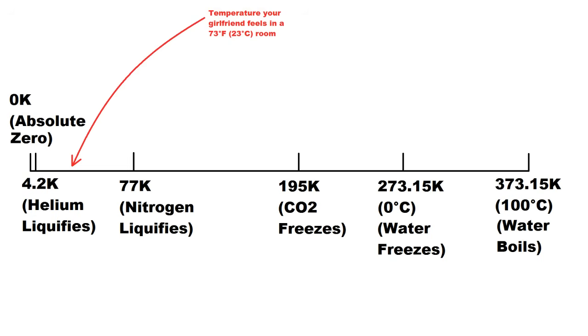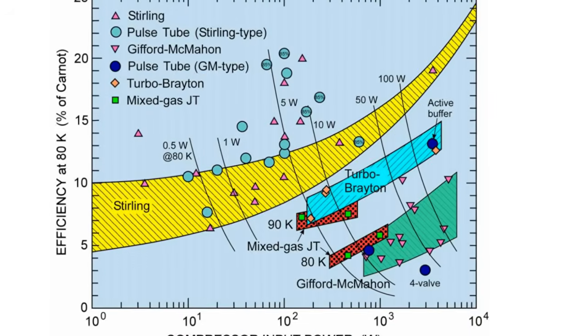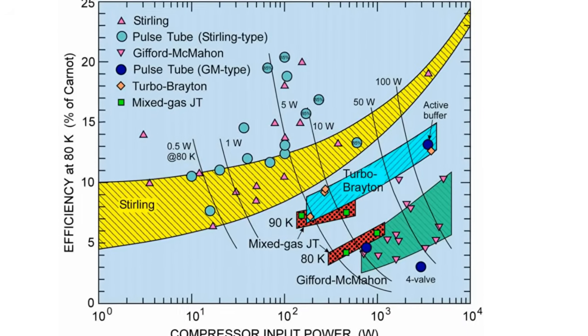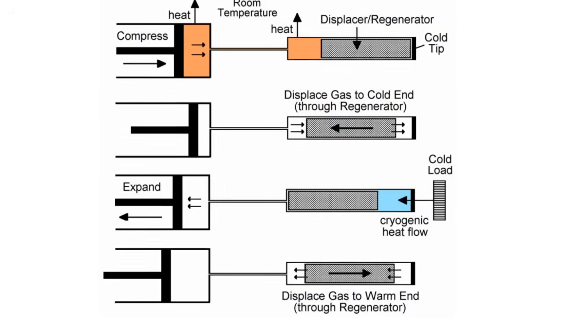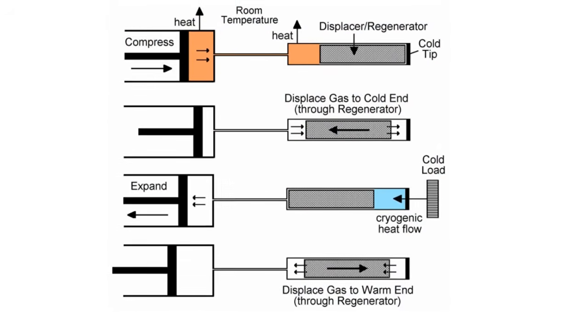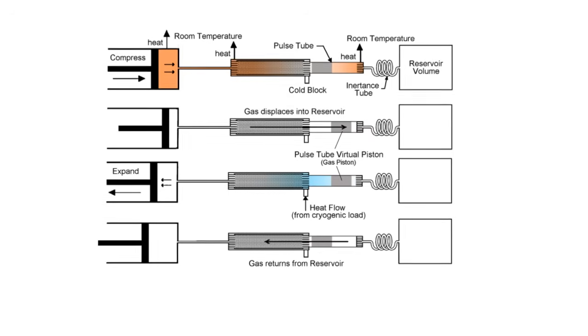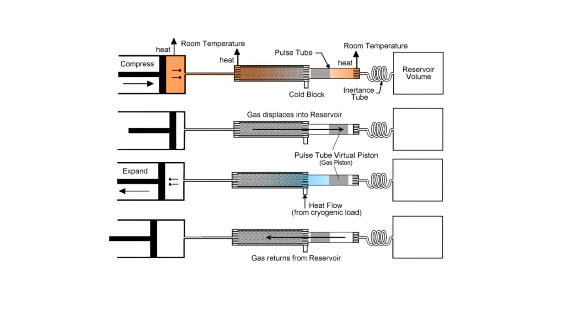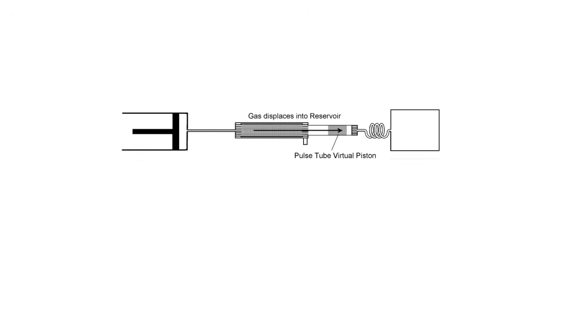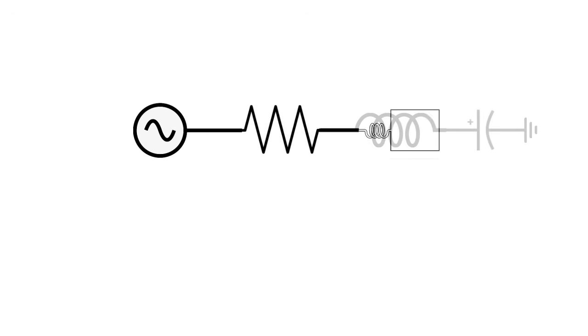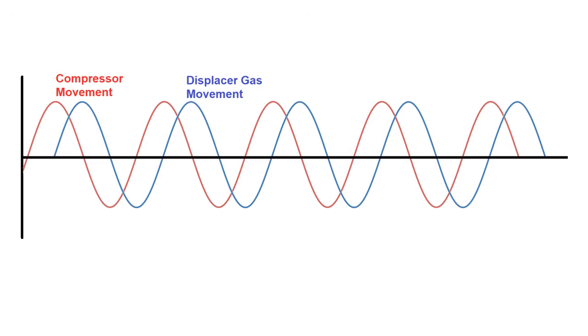A pulse tube isn't necessarily as efficient as a Stirling cycle cooler, but it has the huge advantage that it has no moving parts in the cold end. In the case of a Stirling cooler, a displacer piston moves back and forth in the cold end, but a pulse tube replaces this part with a carefully tuned pneumatic circuit that involves a long tube and a buffer tank, which act like an inductor and a capacitor in an electrical circuit, to create a phase shift between pressure and gas flow, similar to how an LC circuit creates a phase shift between voltage and current.